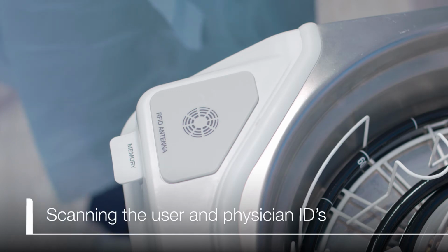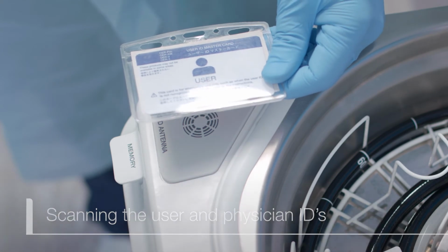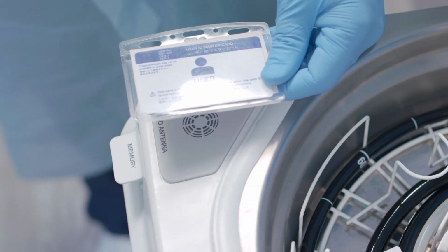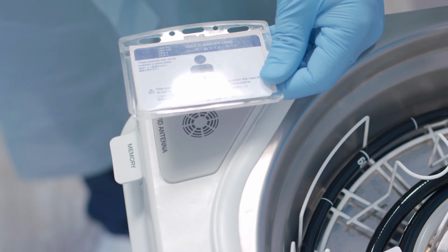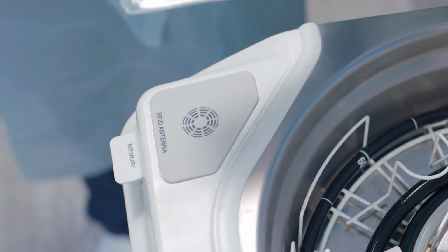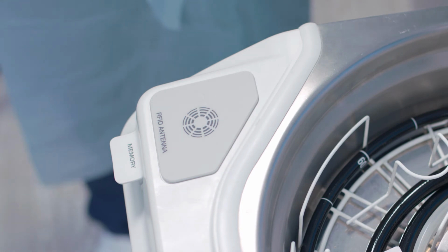Once you've confirmed the scope has been manually cleaned and leak tested, it's time to scan the user ID card. Similar to when we scanned the scope's RFID in our reprocessing log video, we're going to scan the user ID card in the same manner. Simply hold the user ID card over the ID reader section so that the OER-Elite can read the user information. The same can be done with the physician ID card. Again, it's important to note that the user ID card does not need to touch the reader. Simply hold it parallel to the reader, close enough for it to be read.